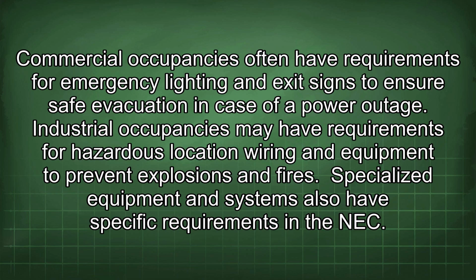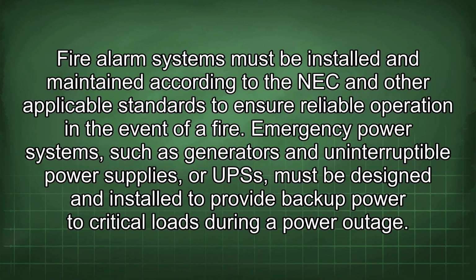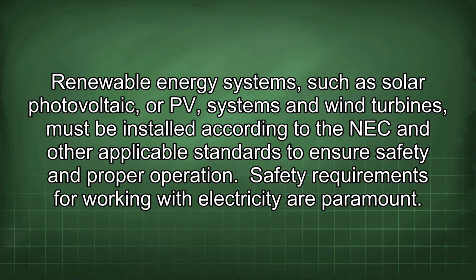Specialized equipment and systems also have specific requirements in the NEC. Fire alarm systems must be installed and maintained according to the NEC and other applicable standards to ensure reliable operation in the event of a fire. Emergency power systems, such as generators and uninterruptible power supplies, or UPSs, must be designed and installed to provide backup power to critical loads during a power outage. Renewable energy systems, such as solar photovoltaic, or PV, systems and wind turbines, must be installed according to the NEC and other applicable standards to ensure safety and proper operation.